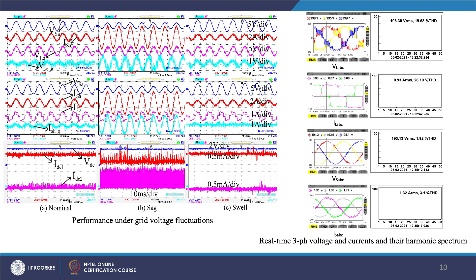With compensation under nominal conditions, the three-phase load voltages V_LABC is around 195 volt line-to-line with 19.68 percent THD, and the load current I_LABC drawn is 0.93 ampere RMS with 26.19 percent THD. Whereas the three-phase source voltage V_SABC is around 192 volt line-to-line with 1.92 percent THD, and source current I_SABC drawn is 1.32 ampere RMS with 3.1 percent THD.